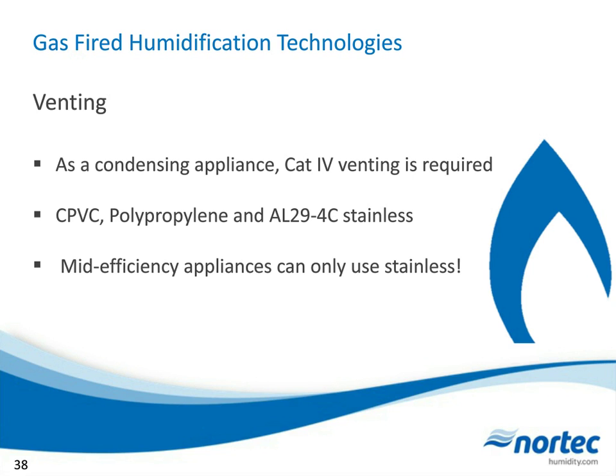As Category 4 appliances, we can now use CPVC or polypropylene venting, or AL 29 stainless special gas vent. You cannot use Category 1 or 2 venting on these products — Category 4 only, meaning it must be a sealed, condensate-approved system. CPVC may or may not be allowed depending on local codes. Polypropylene is newer in North America but established in Europe and allows up to approximately 220–230°F exhaust temperature, whereas CPVC maxes out around 170°F. Stainless steel can handle whatever temperature any gas-fired appliance produces.